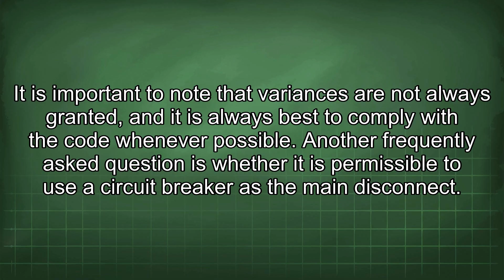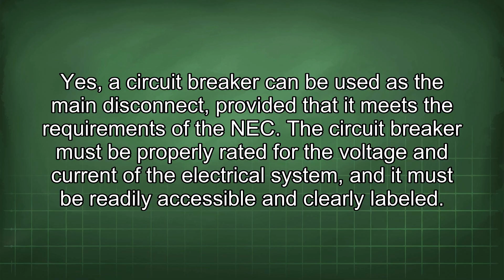Another frequently asked question is whether it is permissible to use a circuit breaker as the main disconnect. Yes, a circuit breaker can be used as the main disconnect provided that it meets the requirements of the NEC. The circuit breaker must be properly rated for the voltage and current of the electrical system, and it must be readily accessible and clearly labeled. It is also important to ensure that the circuit breaker is installed in a suitable enclosure and is protected from damage.